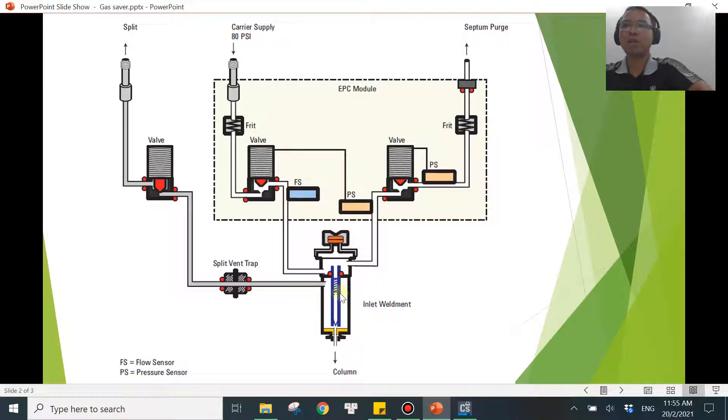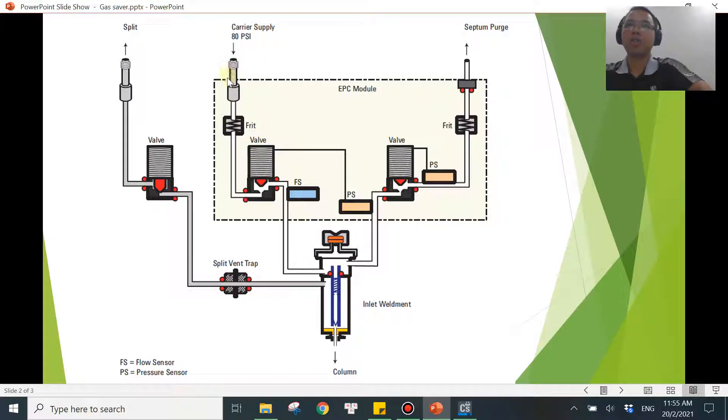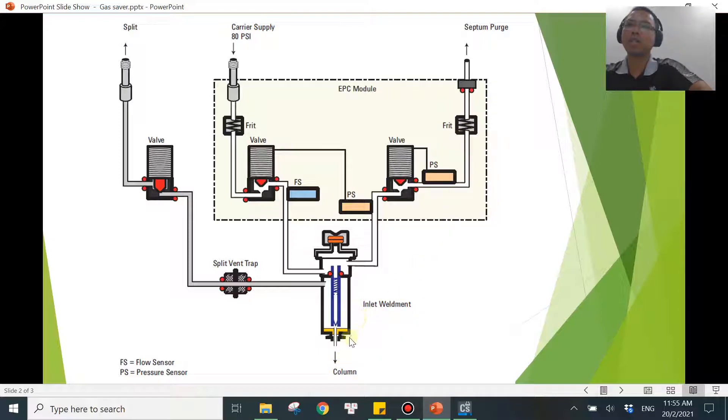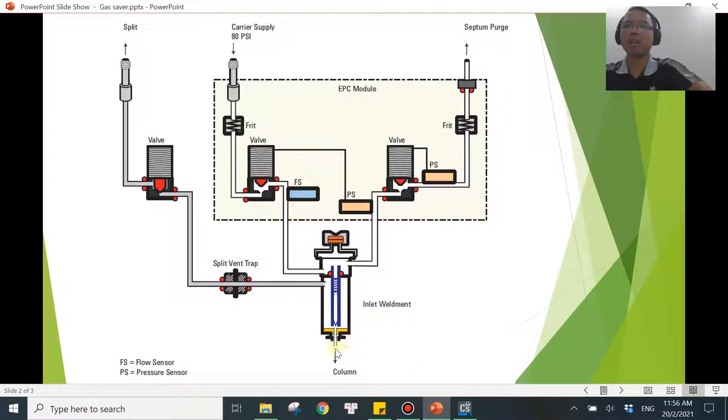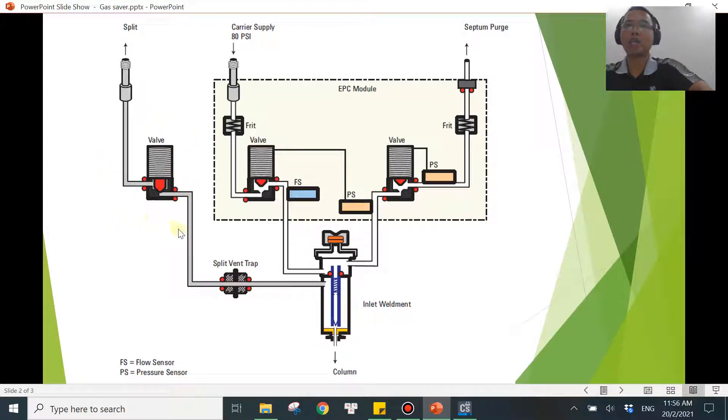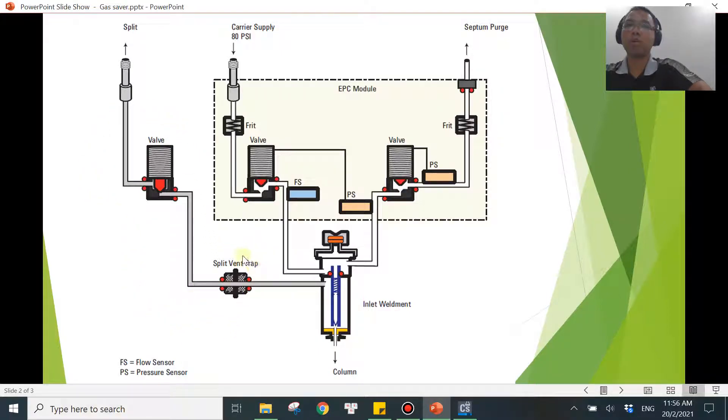Let me show you this one. So the inlet pressure which is inside here, that is designed by the total flow rate that you are sending in over here. And again, a reminder that the total flow rate is a combination of split flow plus the septum flow plus the column flow. So the septum and the column flow, usually you keep them constant. In this case, you keep it at 20 mL per minute over here and 3 mL per minute over here. But this one is something you control, whether you turn on the gas saver mode or not. If you turn on the gas saver mode, this one will become the gas saver flow. If you don't turn on the gas saver mode, this will be the split flow, right?